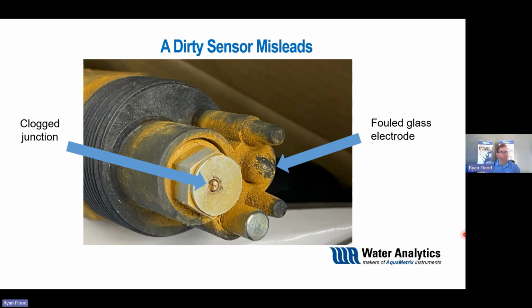Dirty sensors. This is where things can really go wrong. So when you look at a sensor like this and you say, hey, it's just not calibrating, it's going to be an issue, right? There's only so much you can do with calibration. And then if you have a sensor like this, it may just be time to clean. Again, it's really based off of your application. For some people, they can get some readings off of a sensor still like this, and they're happy with it. But if you need a higher level of resolution and you're struggling to perform the calibration and your sensor looks like this, it may be time to clean.